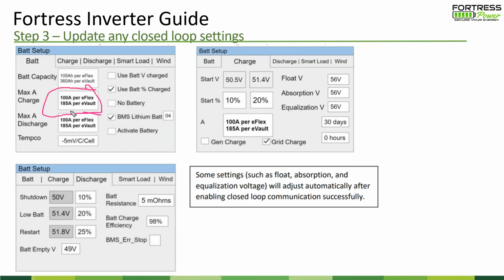And what you'll see is the full range of amperage for the batteries, up to the maximum range to fit the eVault and the eFlex to the Sol-Ark. So for example, that will allow you to do 2 eFlexes onto 1 Sol-Ark with the expanded range and still use the full range of the Sol-Ark for that application because of closed loop. We'll get into the implication of that in a minute. Lastly, because you've programmed in percentage-based controls, you can now program based off percentages instead of voltage levels, and that is much more consumer friendly at the very least.